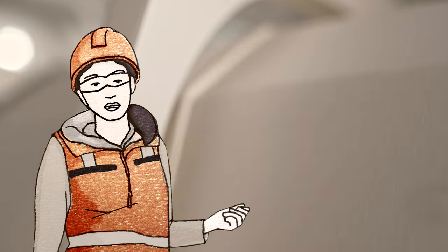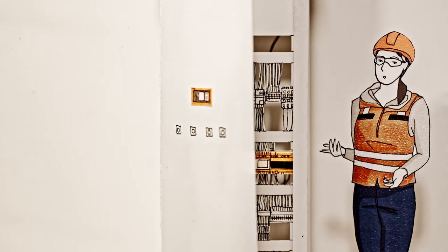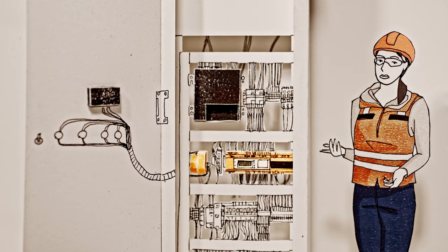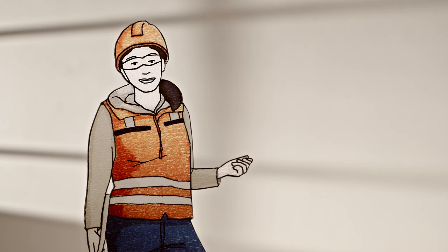For over 75 years, Bender has been a leading manufacturer of cost-effective ground fault detection equipment. Bender has developed an advanced monitoring system for high resistance grounded systems that includes NGR monitoring, fault localization, and second ground fault detection.